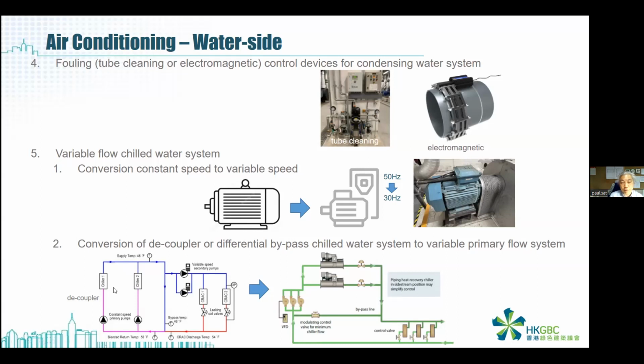And the fifth one is variable flow. We can convert the constant speed pump to a variable speed pump, and we can also convert the constant flow system to a variable flow system. I think the first one is quite common; most people in other countries also convert constant speed devices into variable speed. The key to success is how you control the speed of the devices. We have an example later on the second one, changing the decoupler system into what we call the variable flow system, or the variable primary flow system.